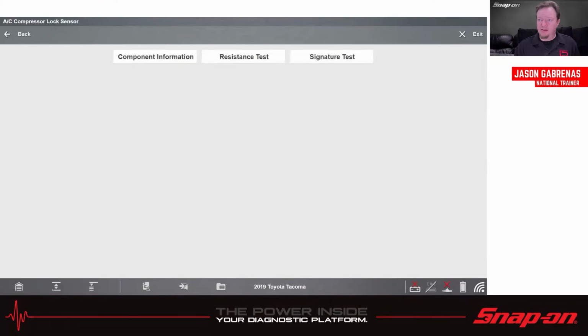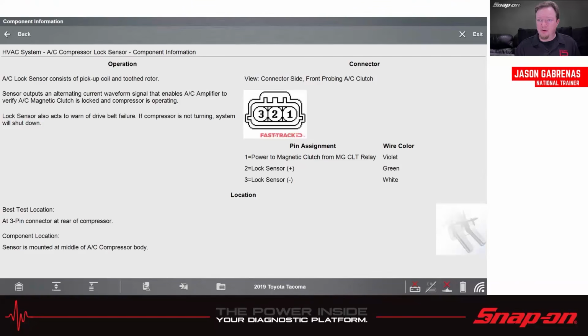If we go into the lock sensor and go into component information, it consists of a pickup coil and a tooth rotor. The sensor outputs an alternating current waveform signal and enables the AC amplifier to verify the clutch is locked and the compressor is operating. It also acts to warn of drive belt failure. If the compressor is not turning, the system will shut down.